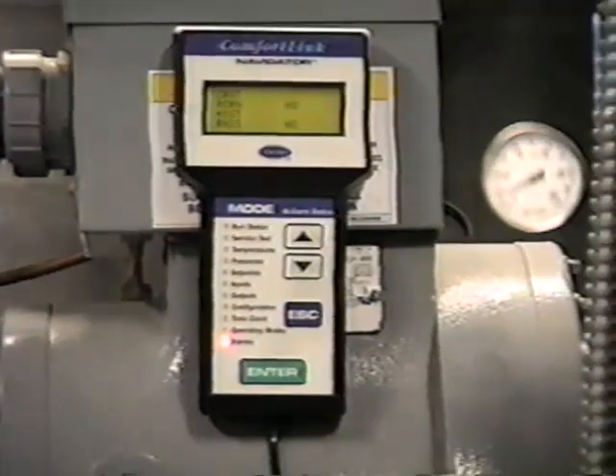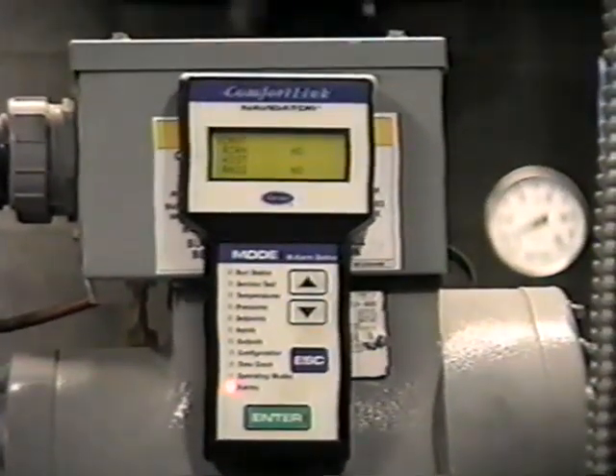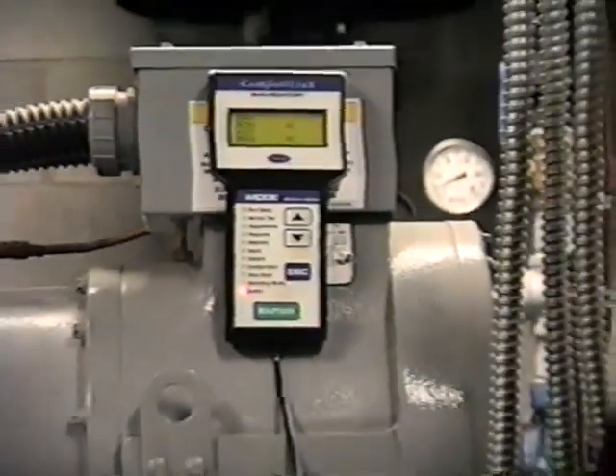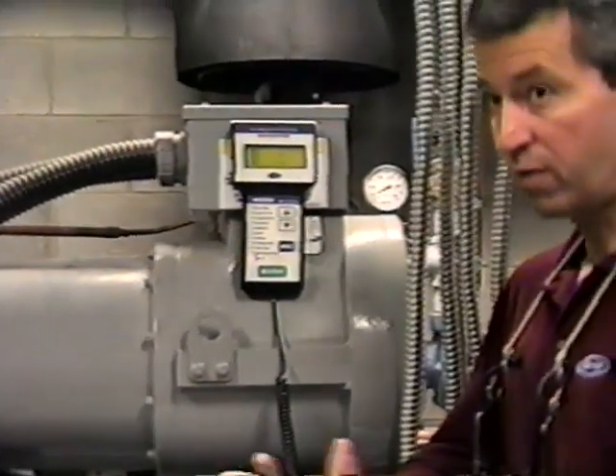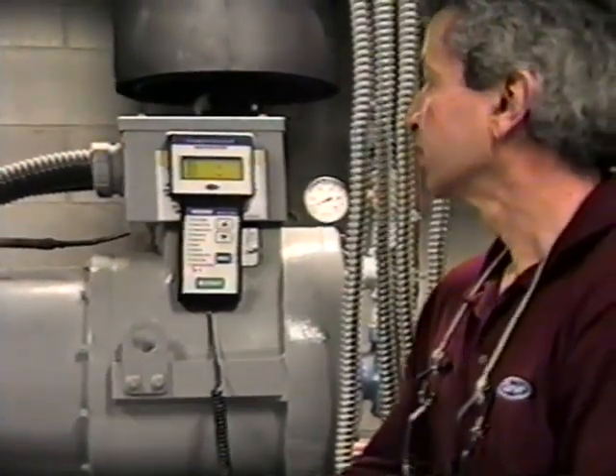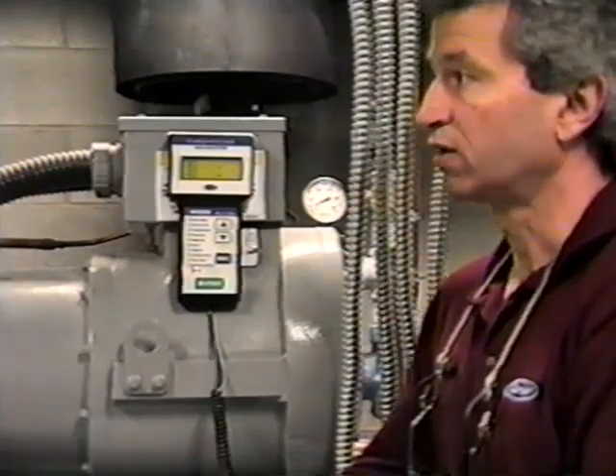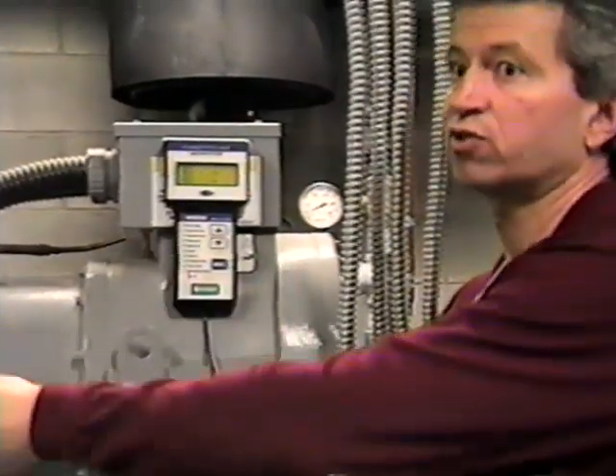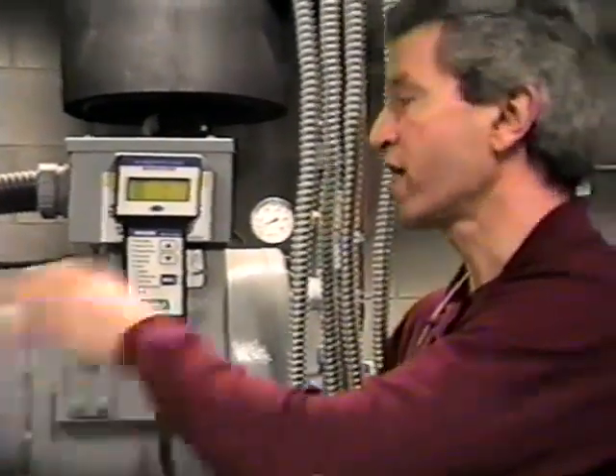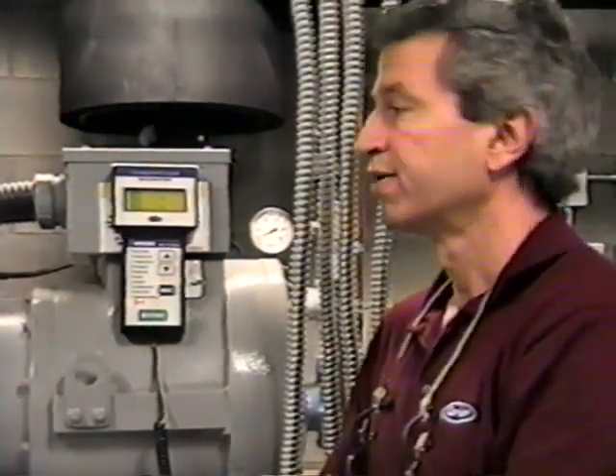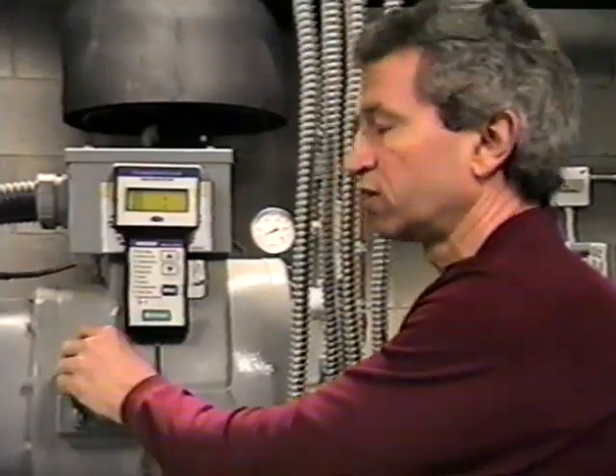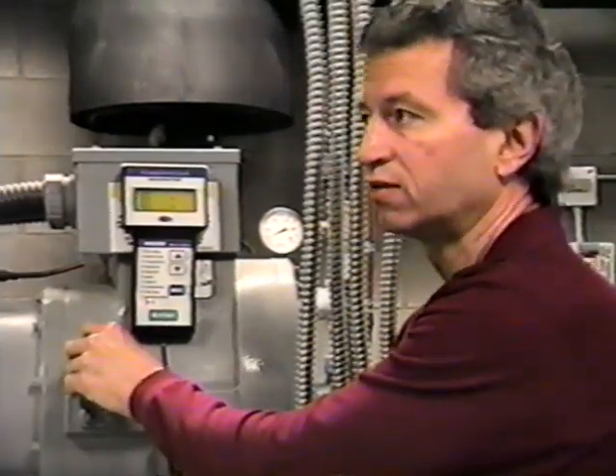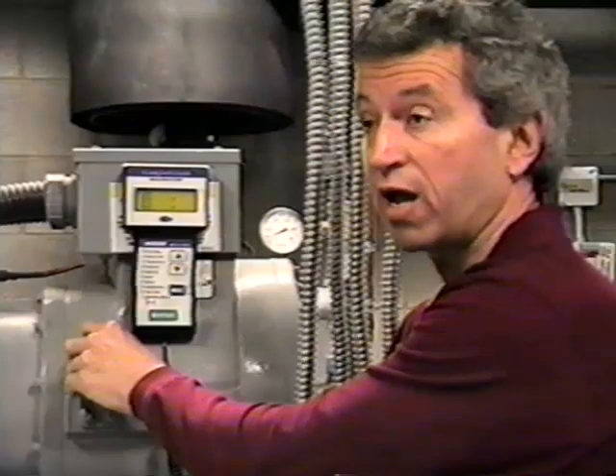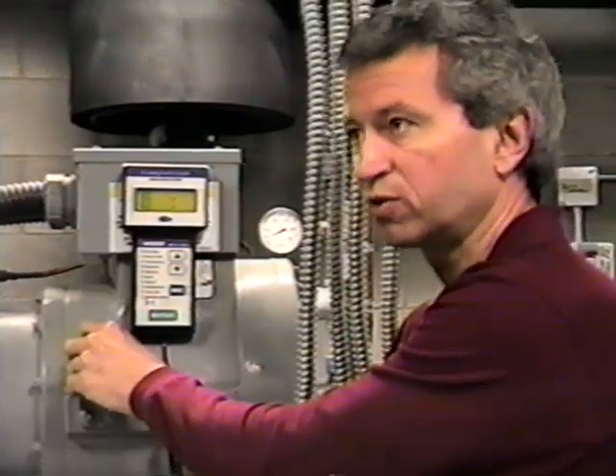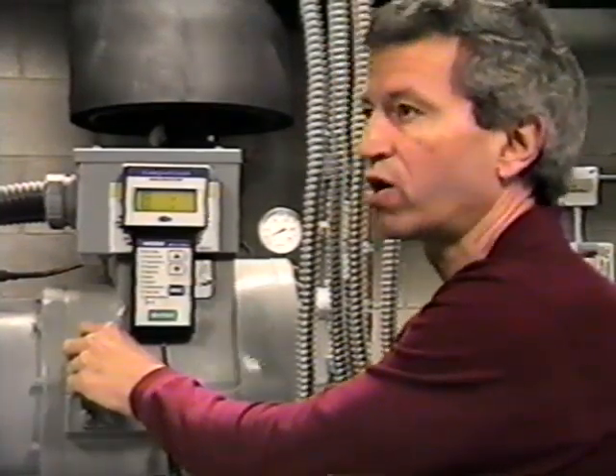We also have alerts that are both manually reset and automatically reset. You could have an alert condition, and an alert condition only affects one circuit or the other. So you're still going to have part of the machine healthy under an alert condition. The other circuit that's in an alert mode may correct itself and start up automatically, depending on what the particular alert is, or it may require a manual reset.